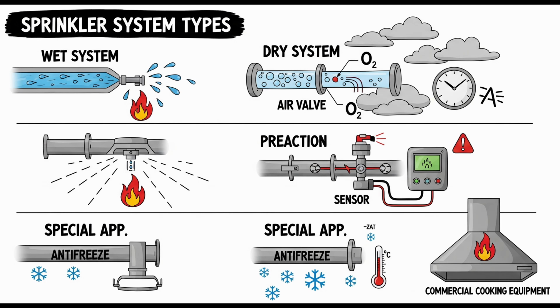What about the water delivery time requirement for these combined systems? Is it like dry pipe or pre-action? It's a specific performance requirement tied directly to the detection system. Water must reach the farthest sprinkler within a time not exceeding 1 minute for each 400 feet of common feed main piping. This time is measured from the moment the heat-responsive detection system operates. 1 minute per 400 feet of main pipe, starting when the detector goes off, not when a sprinkler opens.